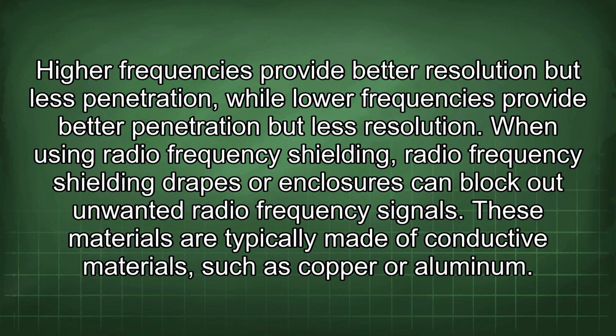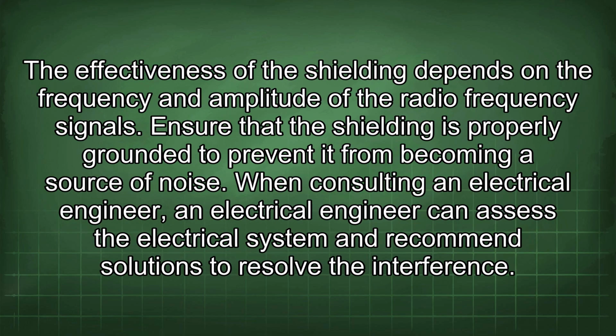When using radio frequency shielding, drapes or enclosures can block out unwanted radio frequency signals. These materials are typically made of conductive materials such as copper or aluminum. The effectiveness of the shielding depends on the frequency and amplitude of the radio frequency signals. Ensure that the shielding is properly grounded to prevent it from becoming a source of noise.